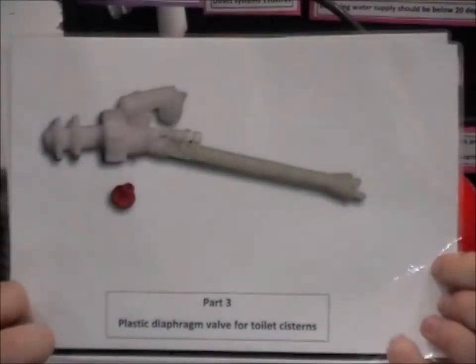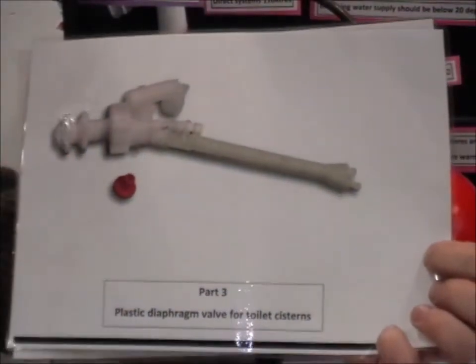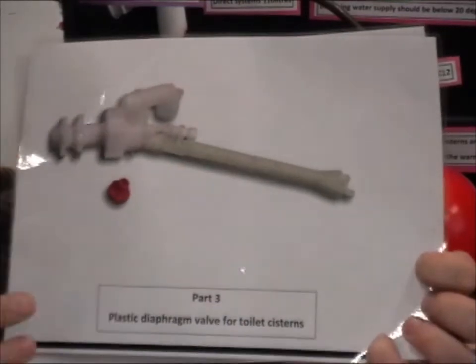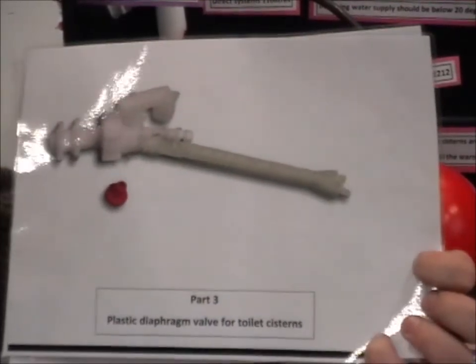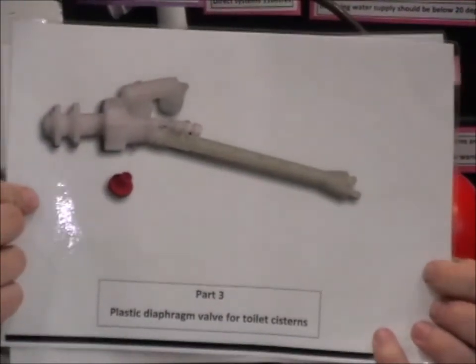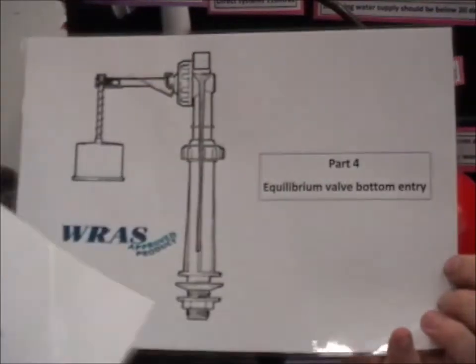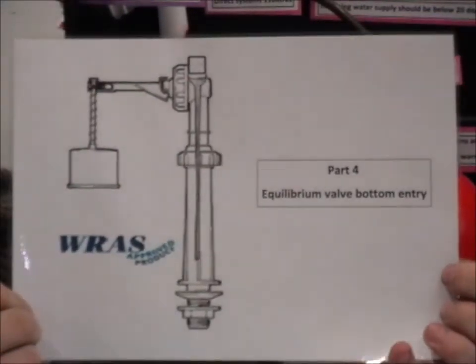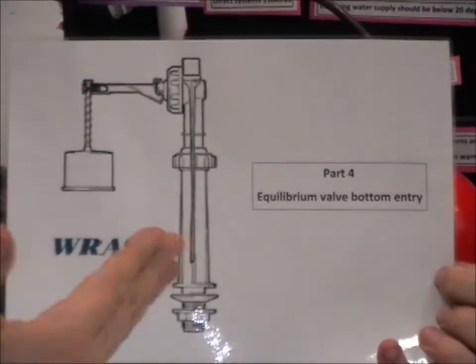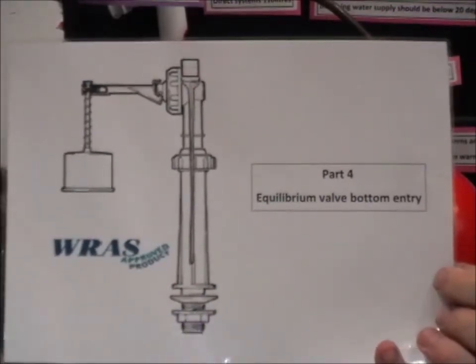Part three ball valve, these can be bottom entry as well, these are for toilet systems. The difference is, this is plastic, can't handle much pressure. Again, same principle, diaphragm washer with an orifice for the seating. Part four is the equilibrium type, where it uses the mains pressure to shut off. You can't use these on low pressure systems.